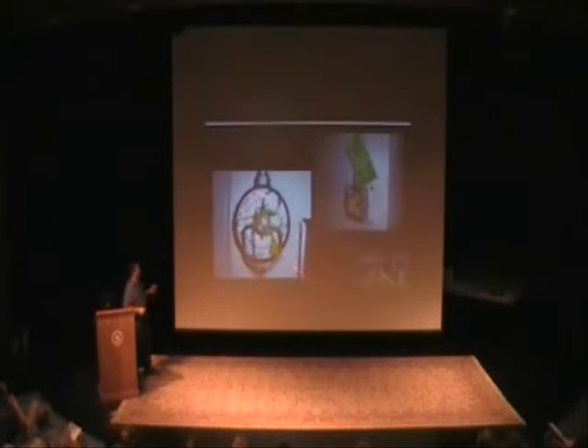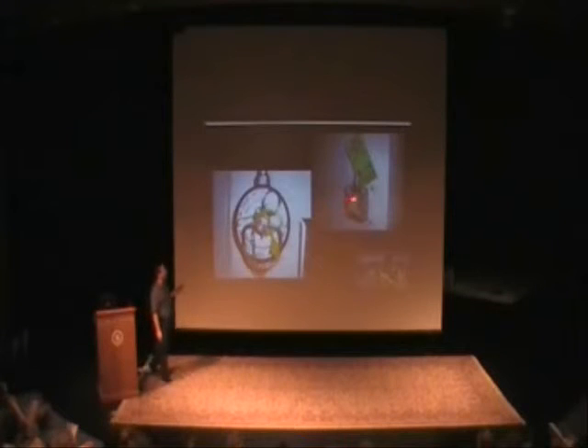This is what your hand pull looks like. Not all of them. This is not all inclusive. If it looks like something like this, you need to call the person on the tag and let them know. They need to come back out and fix it because this is inappropriate. Might not work. It might work. But when you need it, it needs to work.